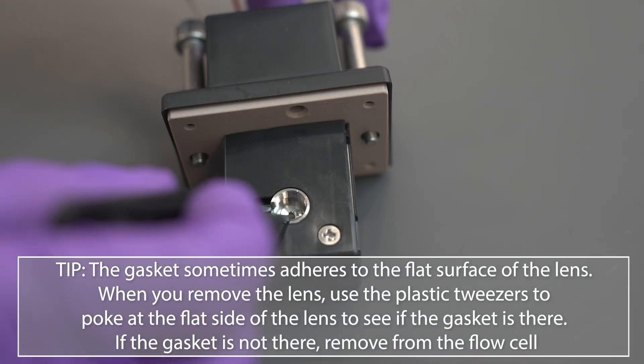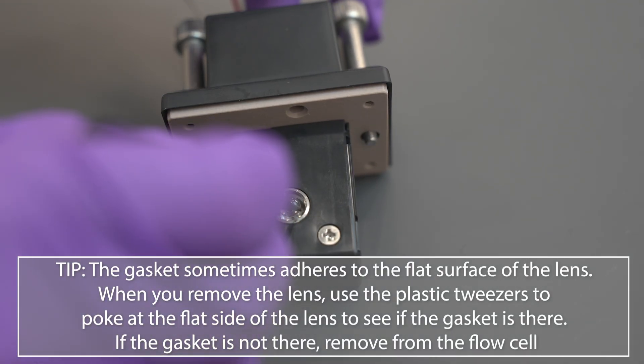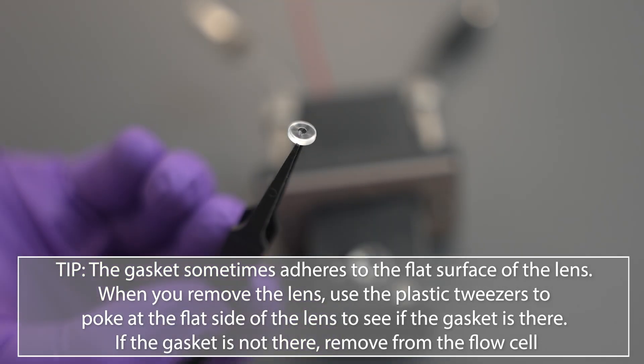The gasket sometimes adheres to the flat surface of the lens. When you remove the lens, use the plastic tweezers to poke at the flat side of the lens to see if the gasket is there. If the gasket is not there, remove it from the flow cell.